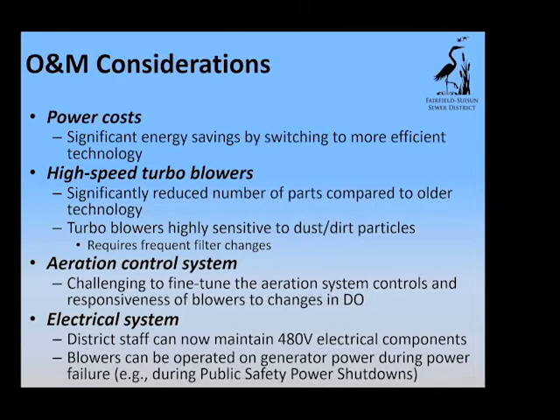I think our recommendation would be, if you go with a new blower system, have the manufacturer send their programmer either on site, or remote in, and put that in the budget so you can pay integrators to work on the system. It took us about 2 weeks just to sit there and fine tune the control loop. It was a lot of work at first, and a steep learning curve for the operators learning this new system, but you put in that work, you get through those 2 weeks, and it's well worth it. It works very well now.